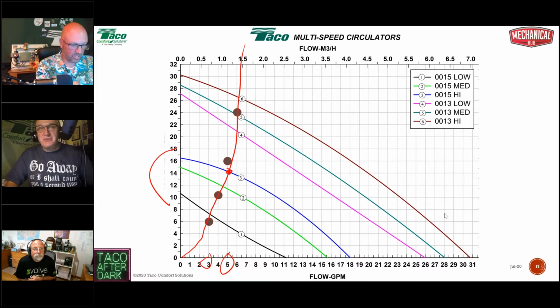Better yet, if I can use a delta T circulator, a VT2218 variable speed delta T circulator, that will vary its speed to try to maintain a fixed delta T within the system for as much of the time as it can, now I've taken that incredible shrinking delta T and given it another monumental whack. So I mitigate that even further.